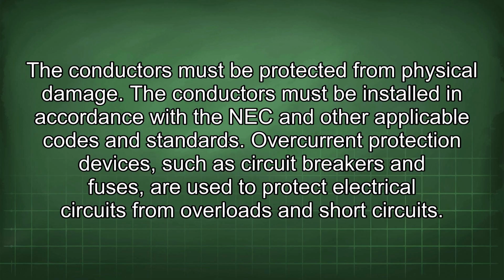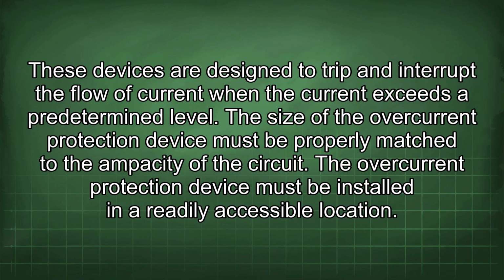Overcurrent protection devices, such as circuit breakers and fuses, are used to protect electrical circuits from overloads and short circuits. These devices are designed to trip and interrupt the flow of current when the current exceeds a predetermined level. The size of the overcurrent protection device must be properly matched to the ampacity of the circuit.